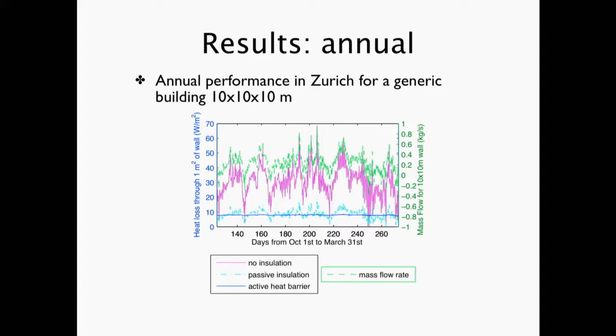So in that sense, we can achieve a thinner construction. On top of that, because we're using ground temperature, which is constant, one of the other issues when supplying heat to a building is that it changes constantly as outside temperature fluctuates. Now we've made this a constant number, so all those machines and controls that have to meet changing demand inside the building can just supply a steady amount of heat, increasing their performance as well.